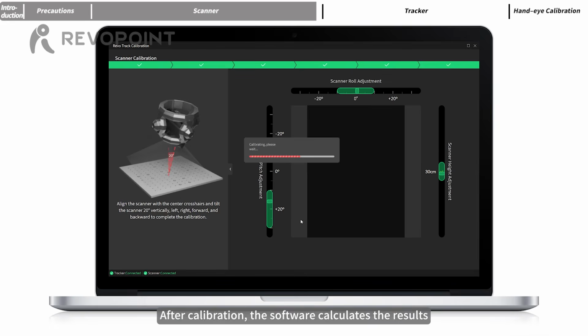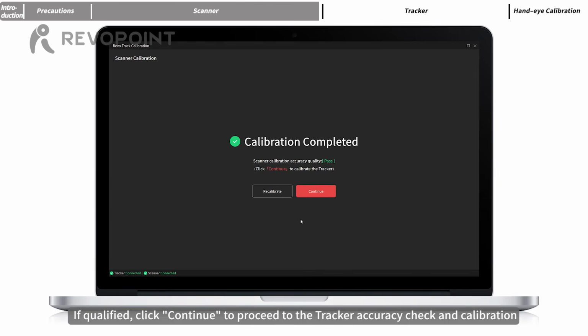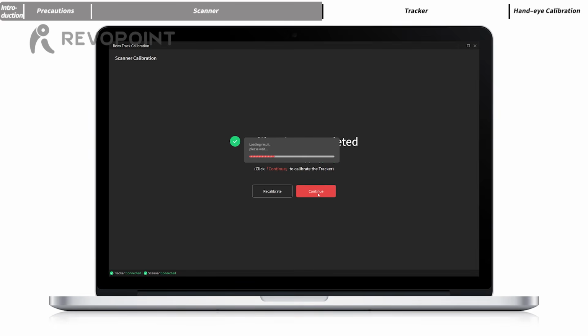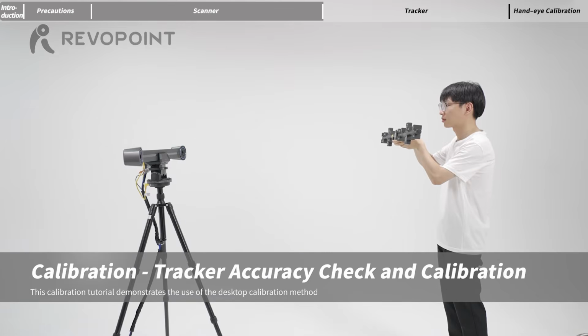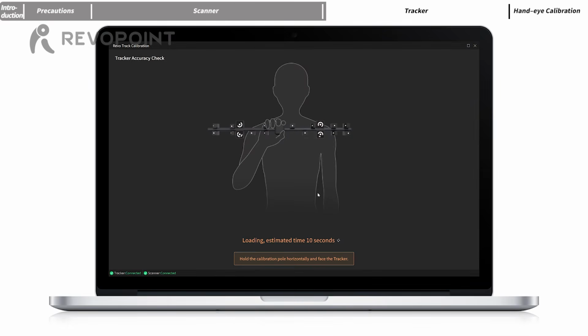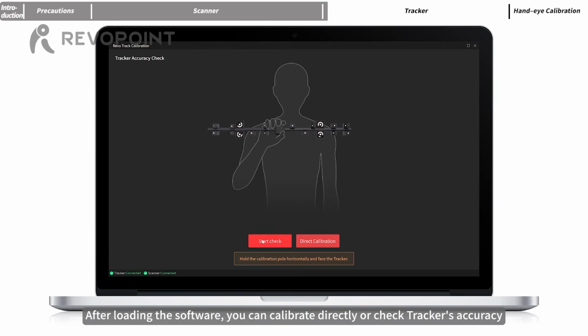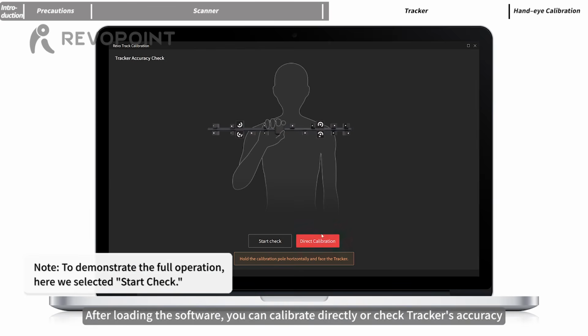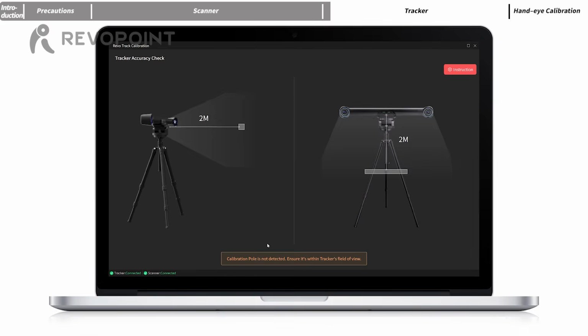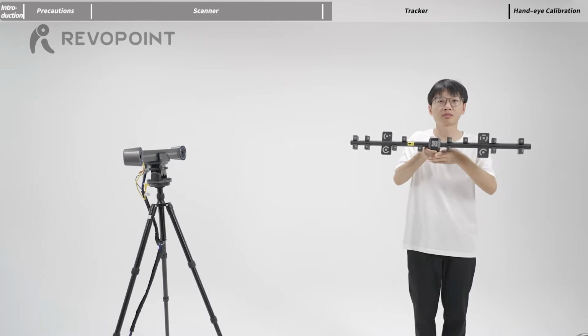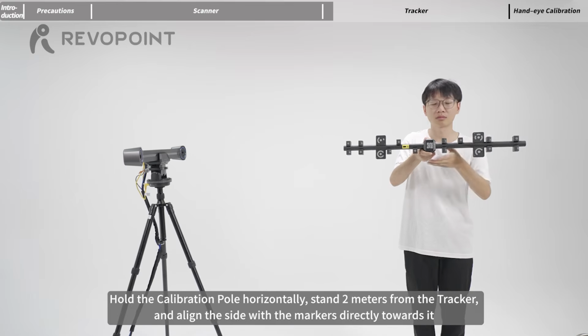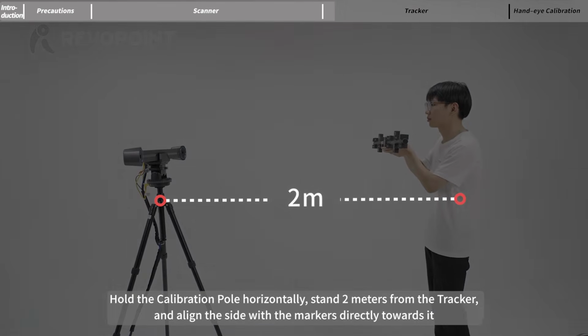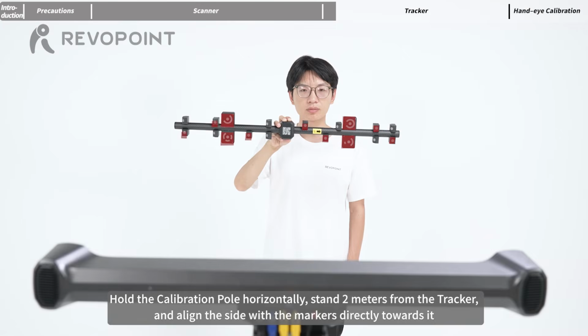After calibration, the software calculates the results. If qualified, click Continue to proceed to the tracker accuracy check and calibration. After loading the software, you can calibrate directly or check the tracker's accuracy. Hold the calibration pole horizontally, stand 2 meters from the tracker, and align the side with the markers directly towards it.